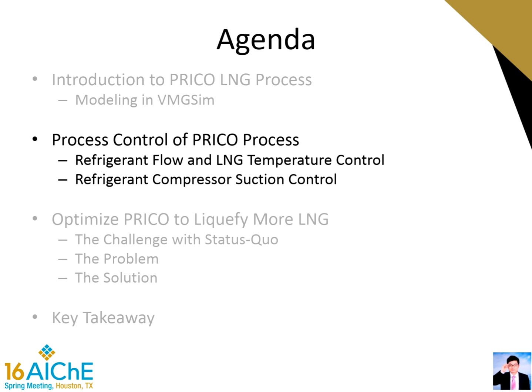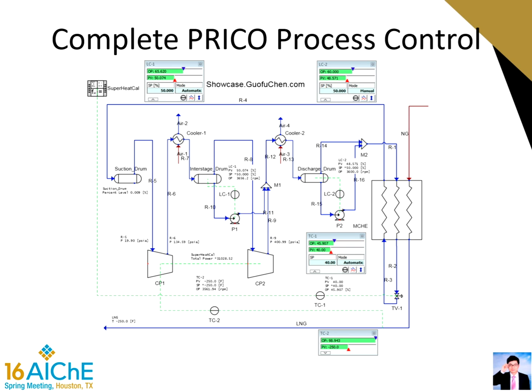Now we move to the process control of the PRICO process. Two major control loops will be particularly discussed: the first is the refrigerant flow and LNG temperature control, and the second is the compressor suction control. Four control loops are modeled in total. TC1 is used to control the compressor suction. TC2 is used to control the LNG outlet temperature. LC1 and LC2 are used to control the liquid level in the interstage drum and discharge drum. Notably, there is no compressor discharge pressure control — the compressor discharge pressure is self-balanced in this cycle. There may also be two additional controllers to control the outlet temperature of the two coolers.